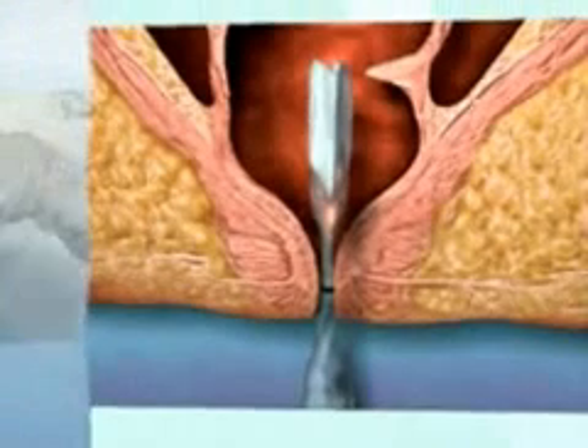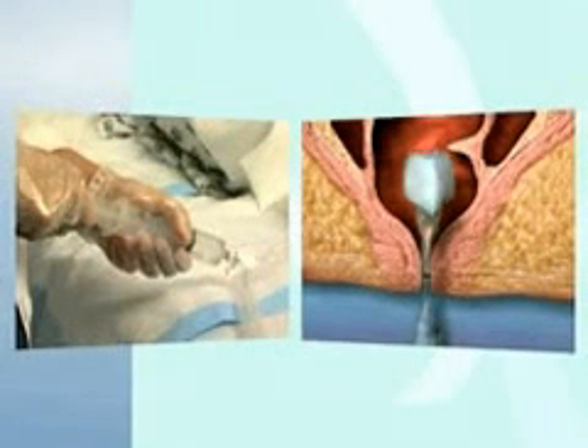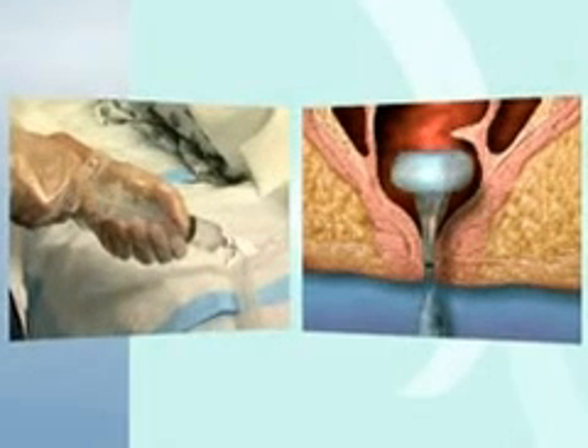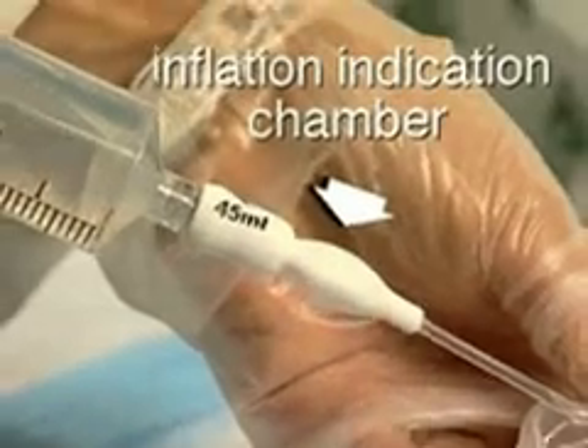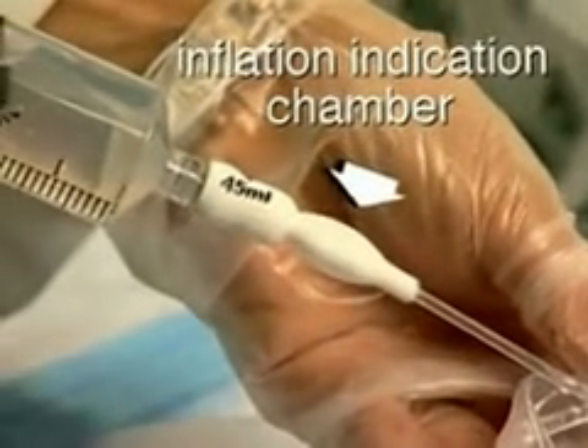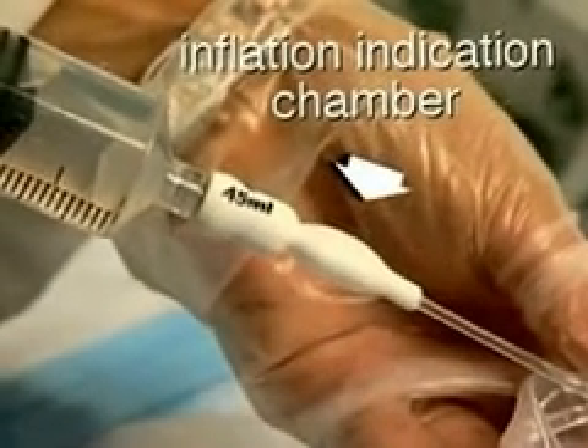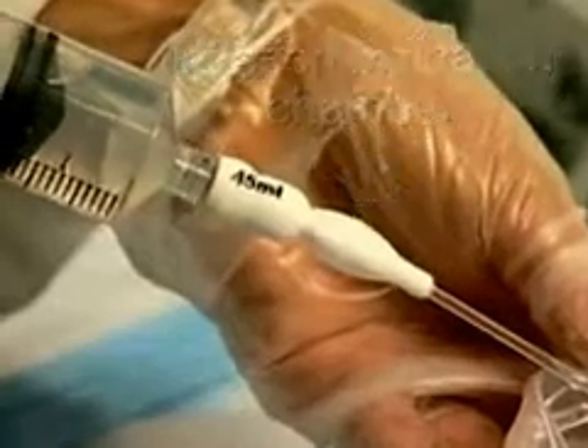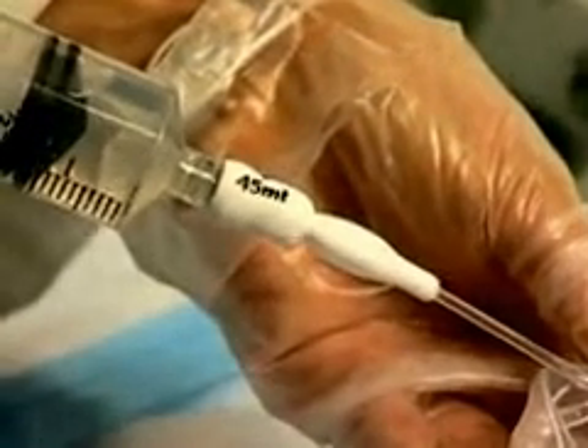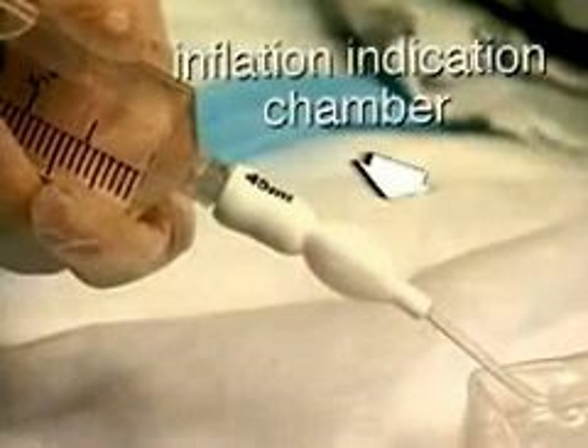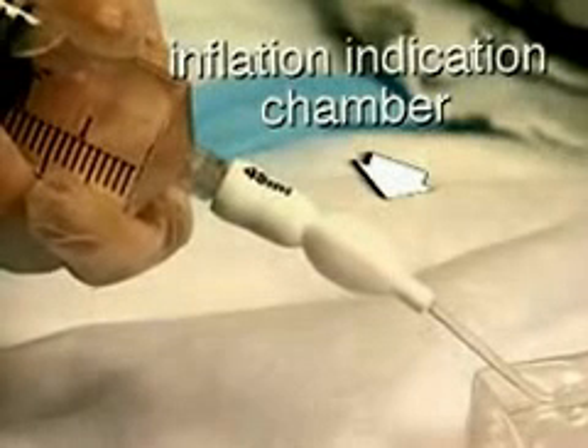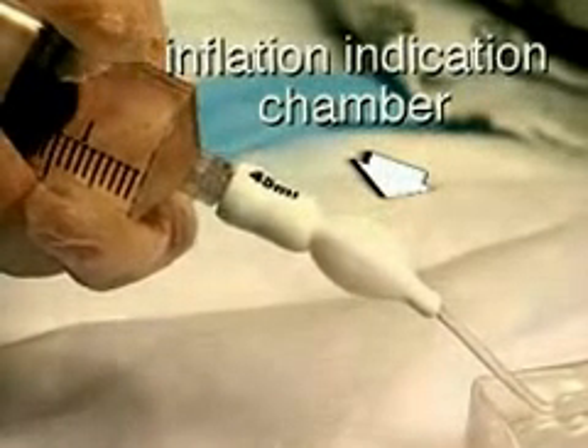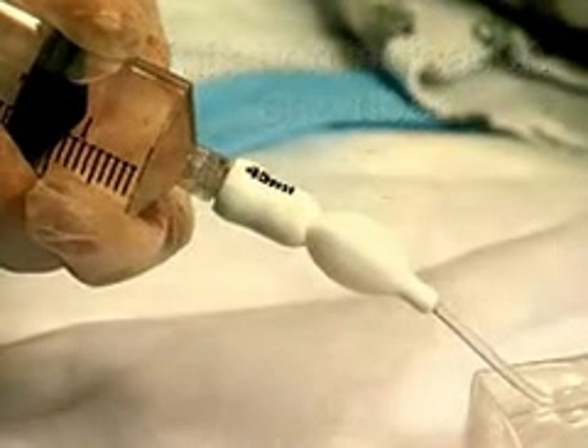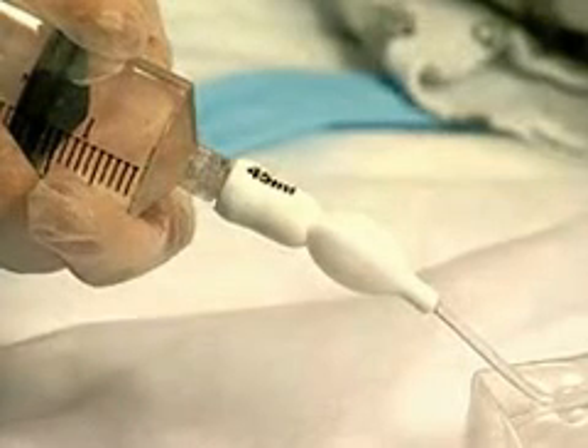Inflate the balloon with 45 milliliters of water or saline by slowly depressing the syringe plunger. The inflation indication chamber on the inflation port will expand as fluid is injected. This normal expansion should subside once the plunger stops. If the inflation indication chamber remains excessively expanded after the plunger stops, the balloon is not properly inflating.